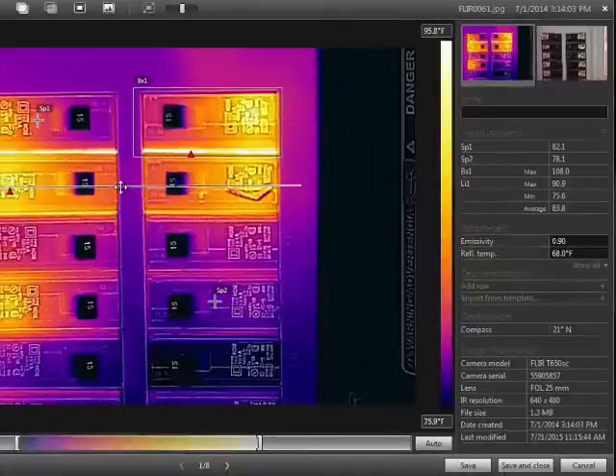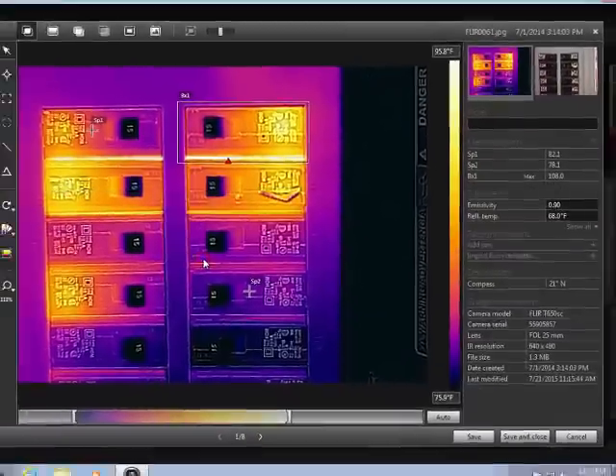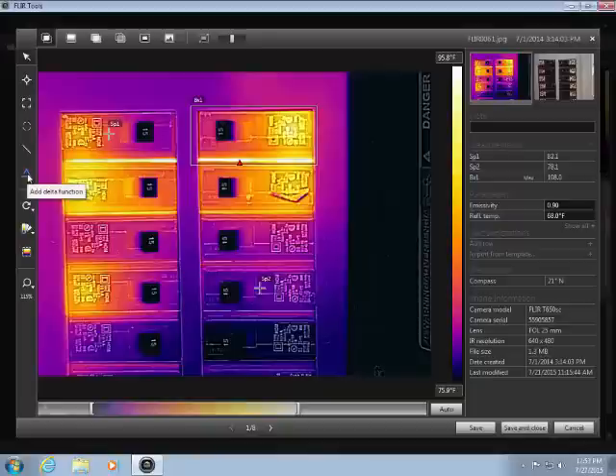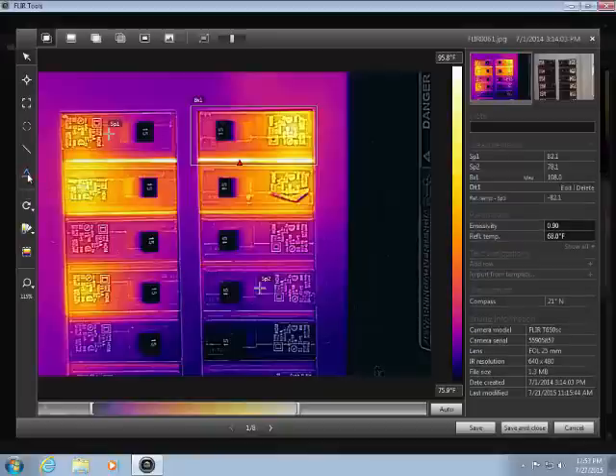You can right-click on any tool to delete it from the image. Using the Difference function, you can calculate a temperature rise, which can be helpful in assessing the severity of certain faults.